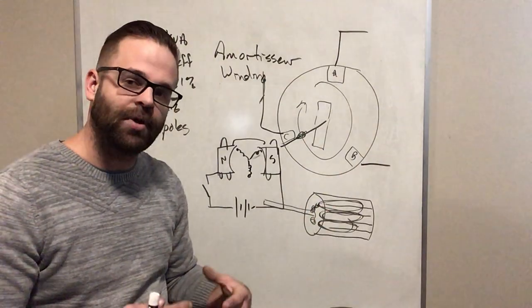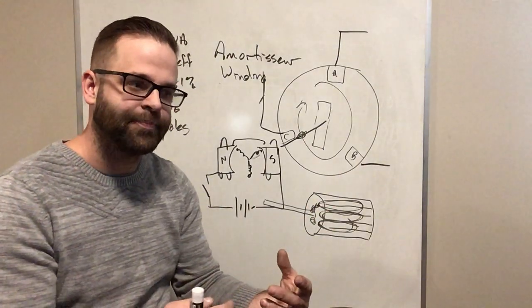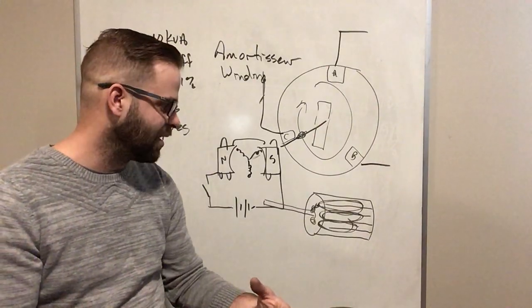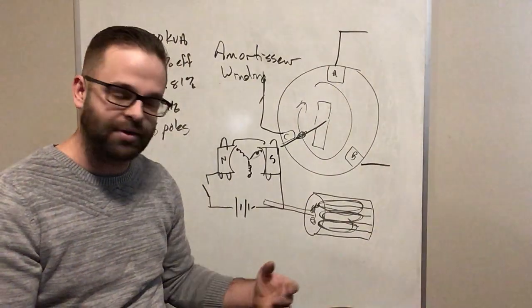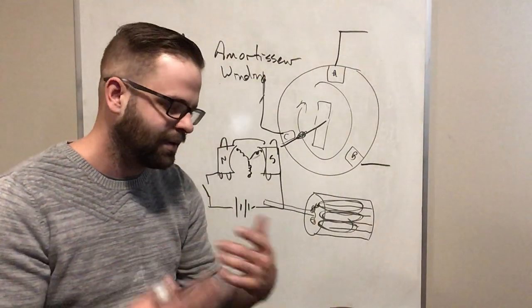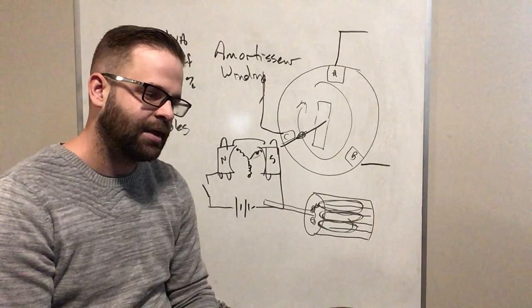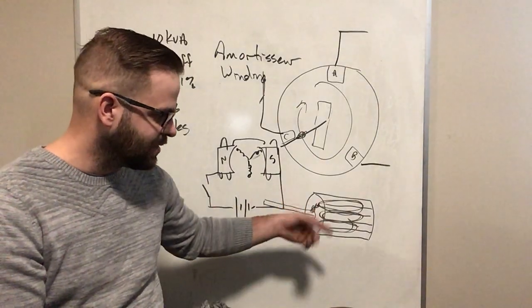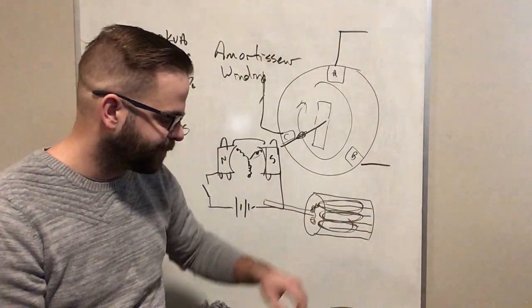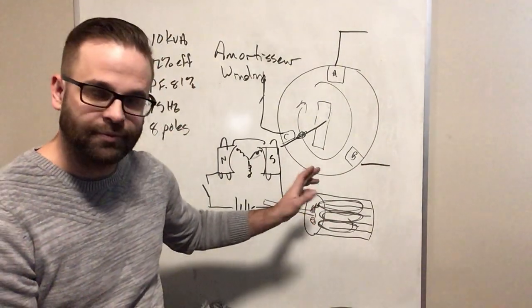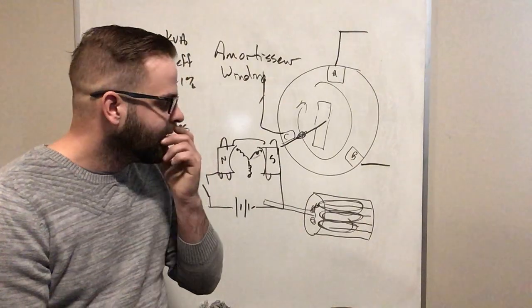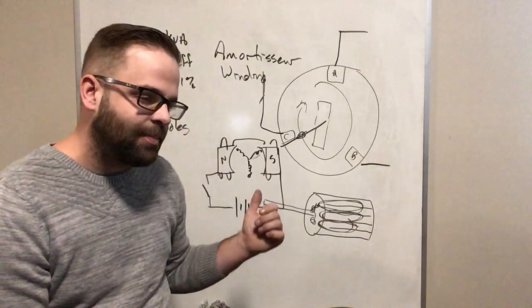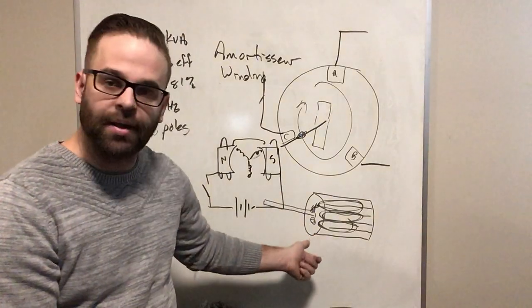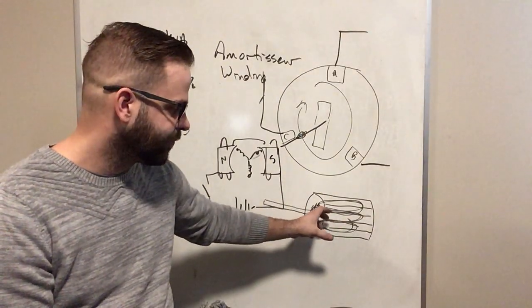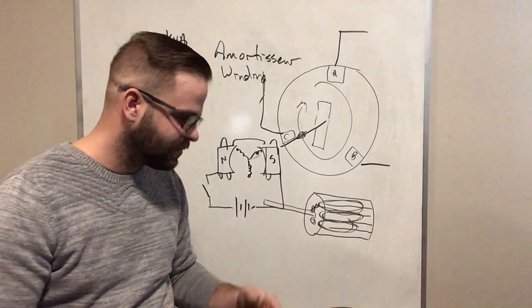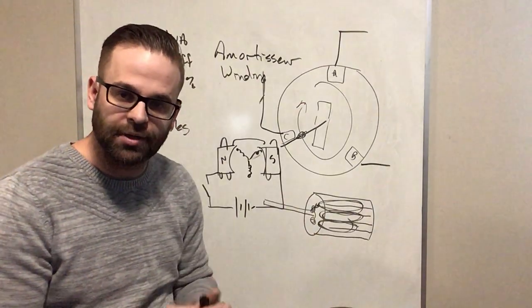So even if it was going to be able to get close or right up to that speed, it would end up falling back a little bit because it would lose its magnetism. So even if it got there on startup and ended up going the same speed, it would fall back a little bit because I need to have some lines of flux being cut to induce that voltage, current, and magnetic field. With that being said, I can't load this down or run it for a long period of time just with the amortisseur winding creating that motion of that motor.